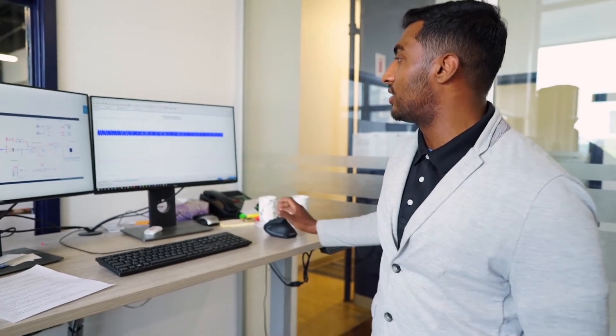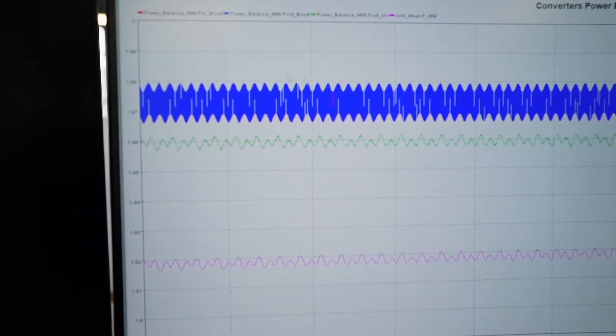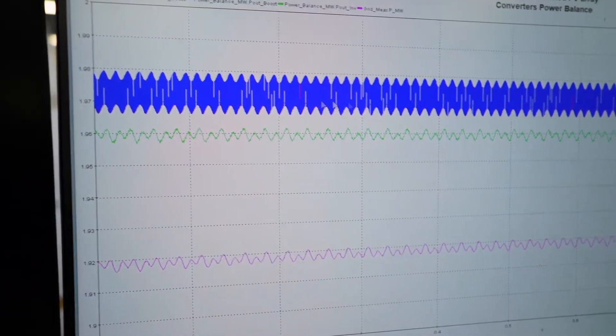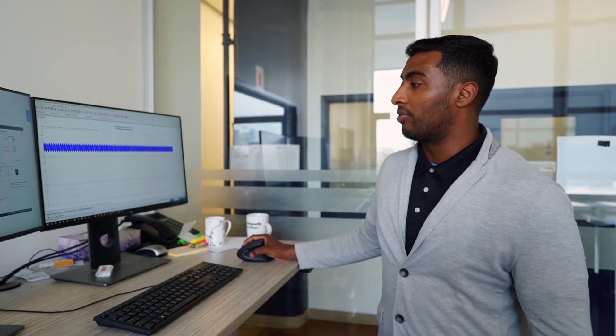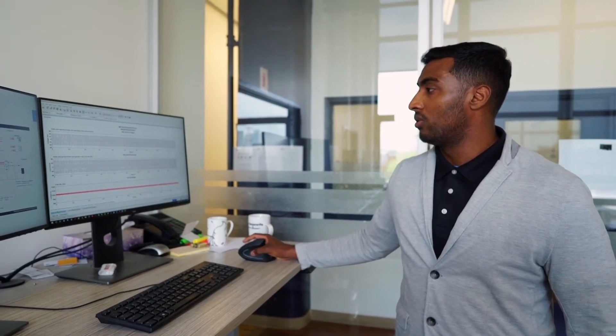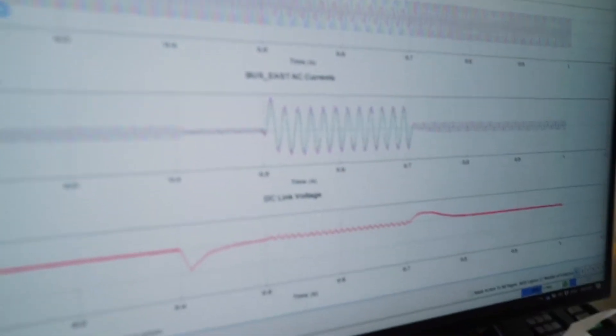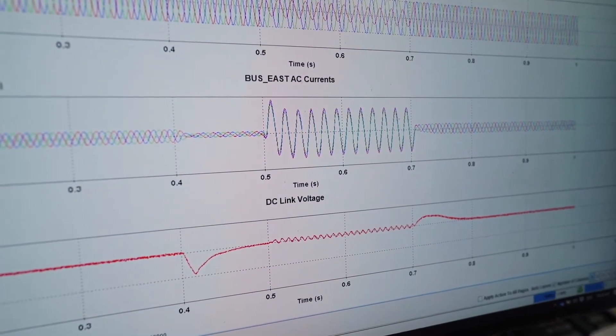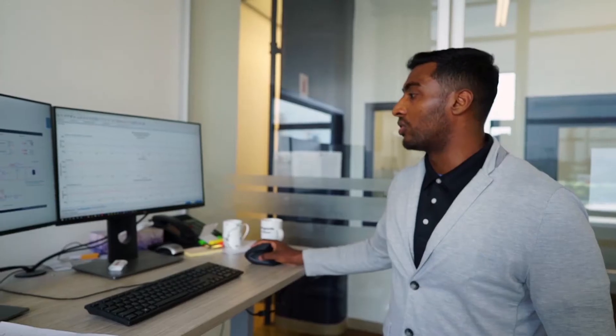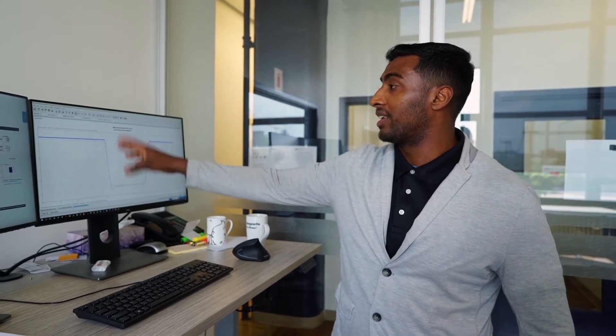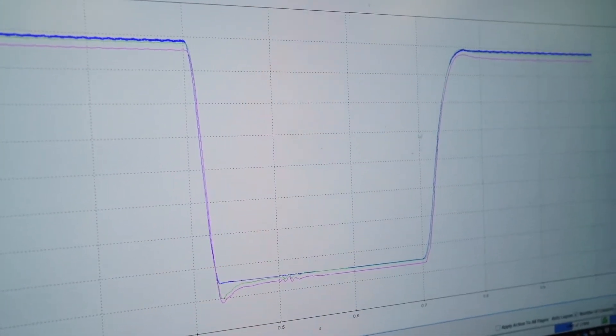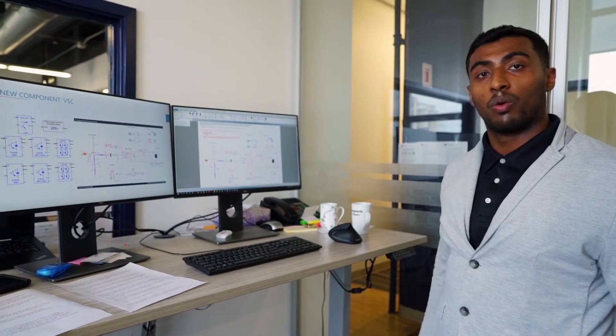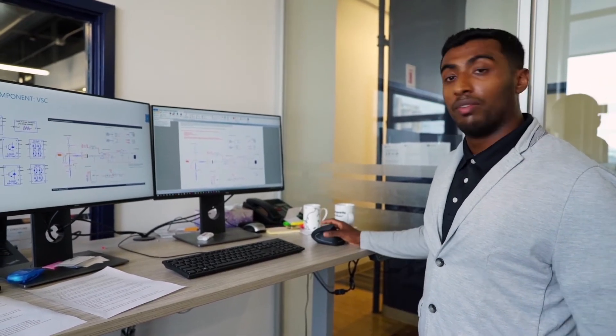Going back to the converter power balance, this is pretty cool actually. You can see the different power balances being shown at different stages of the model. We see that closer to the PV, the power balance is much more. We see the value decreasing as we go on to the feeder. So what we're going to do now, we're going to quickly apply a fault at a specific location and see how that's affecting our circuit. I'm going to click on trigger here and press play again in scope view. As I do this, you can see there's some disturbance in the network and this is also shown in the control measurement section in scope view. If you go into the converter power balance section, we see how applying that fault is affecting the power balance throughout the grid. That's a quick show of our model that is available actually in our HyperSim examples. Anybody that downloads HyperSim from our website is able to see this model and play with it. Feel free to play with it.